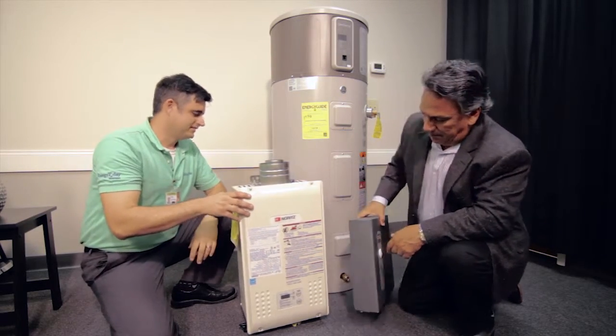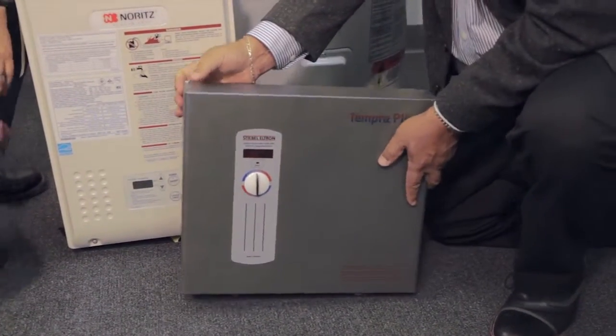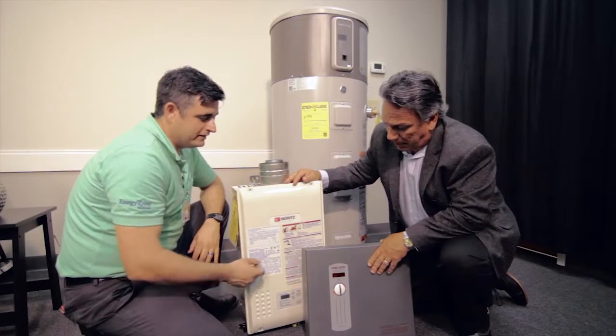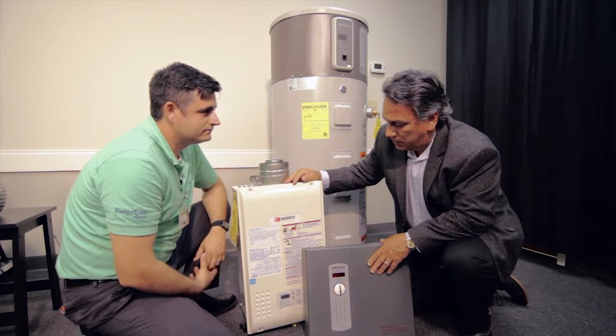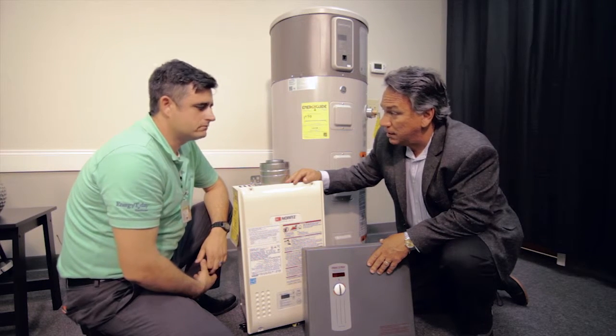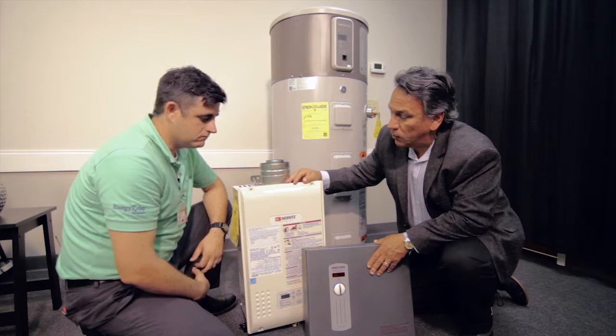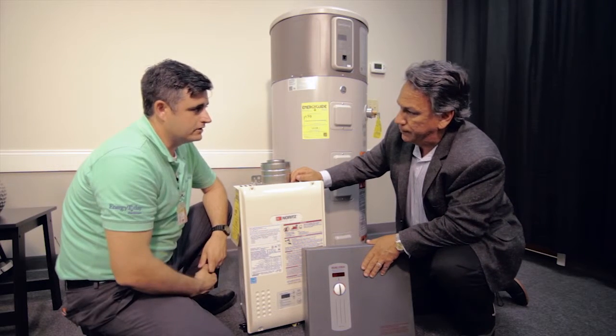This little unit is an electric tankless water heater. It's not recommended for energy efficiency or practical use in most cases — it only saves energy when you're not using any water. It draws about 120 amps, and some services are only 100 amps, so you'd have to upgrade your electrical service. It's best suited for a condo with limited space, a couple of people, or a dedicated mother-in-law suite.